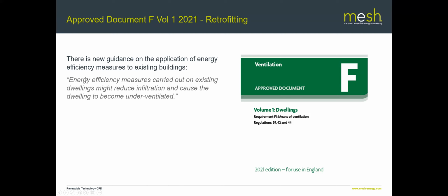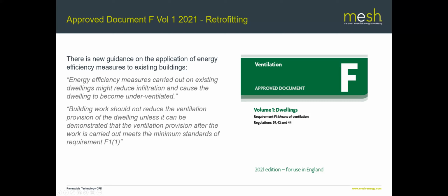So the requirement now is that energy efficiency measures carried out on existing dwellings might reduce infiltration and cause the dwelling to become underventilated. Building work should not reduce the ventilation provision of the dwelling unless it can be demonstrated that the ventilation provision after the work is carried out meets the minimum standards requirement of F1, which is basically saying it's got to meet the requirements of the approved document. So if you do reduce the infiltration, you need to make sure that you're still providing sufficient ventilation to the building.